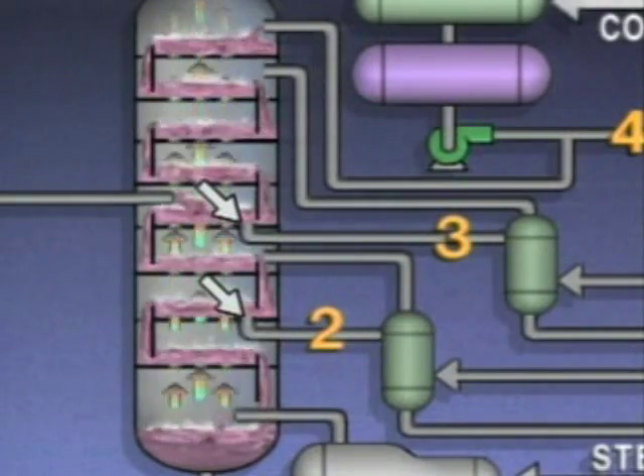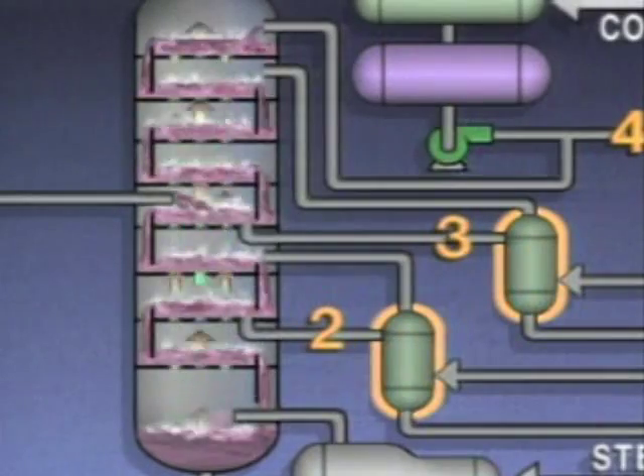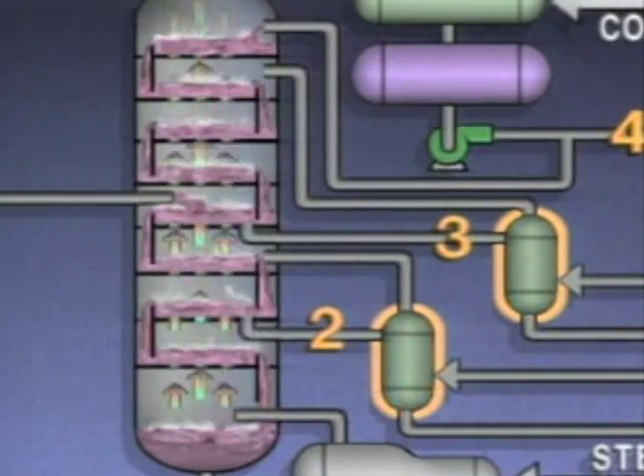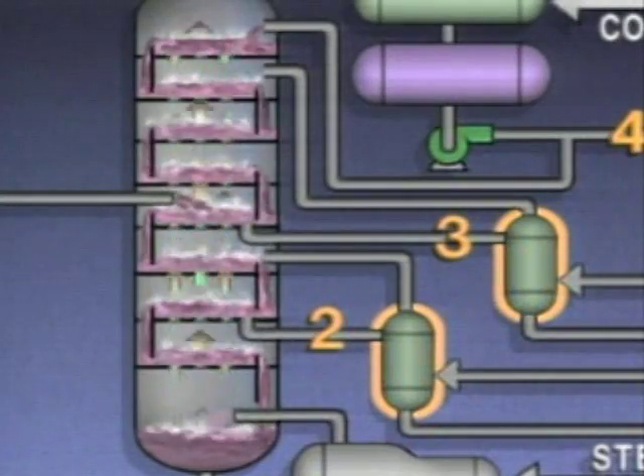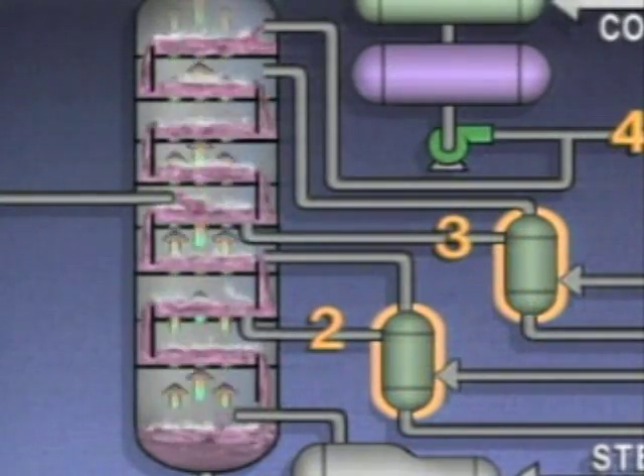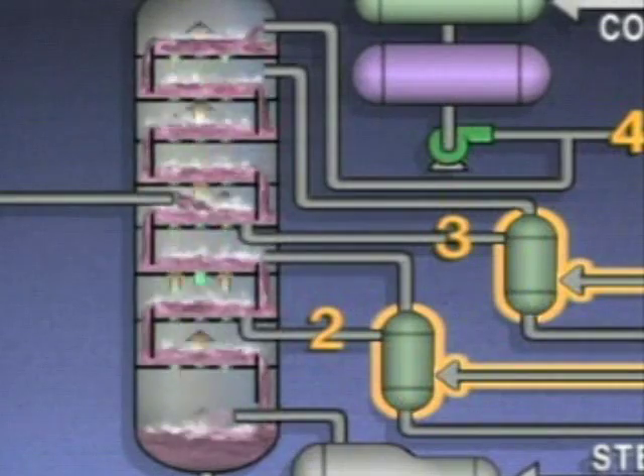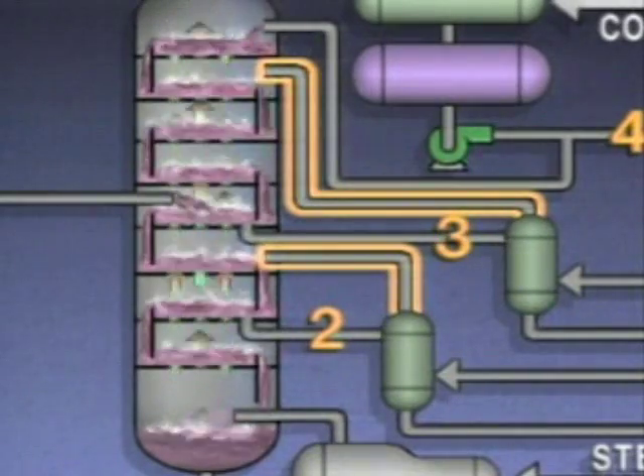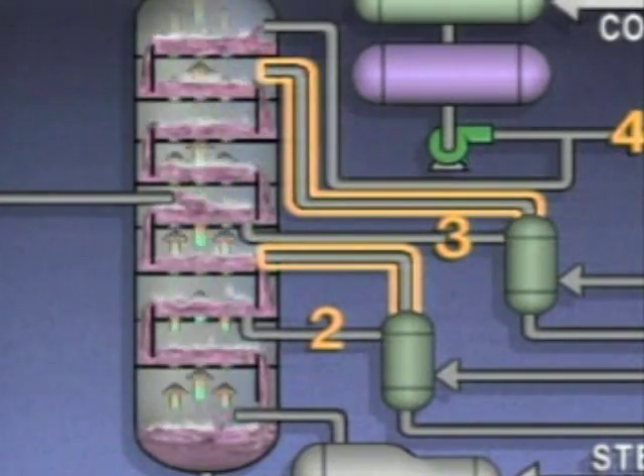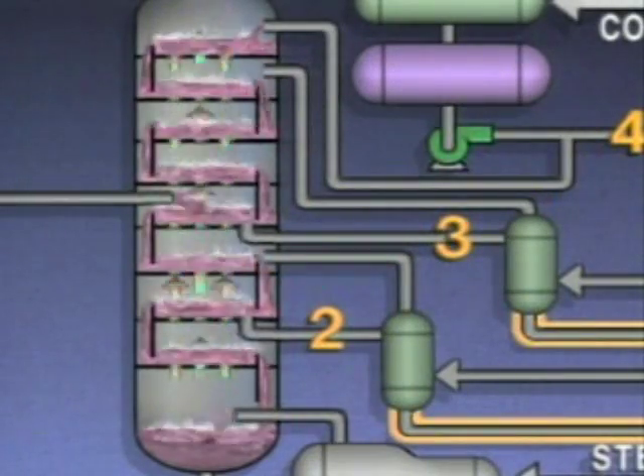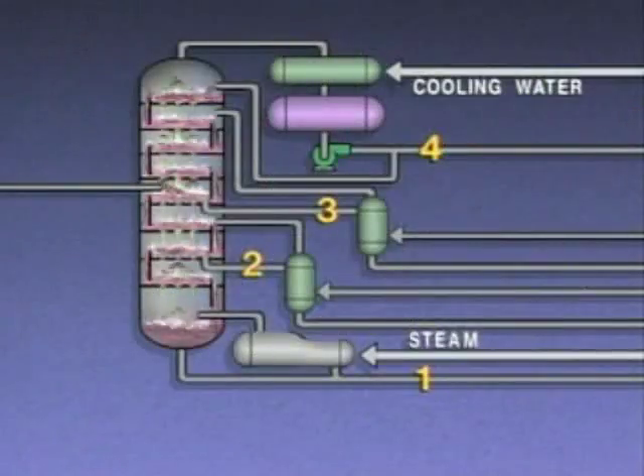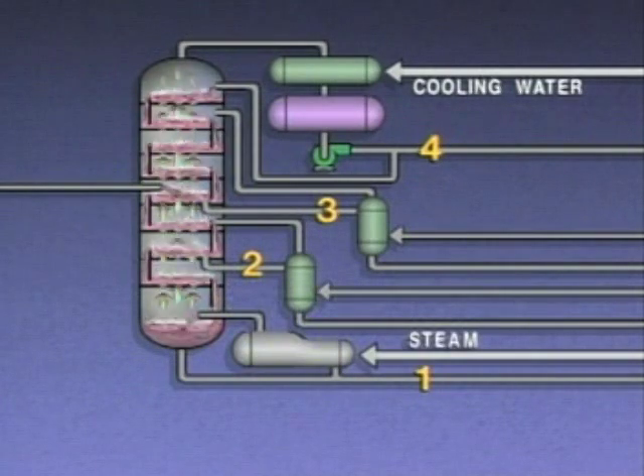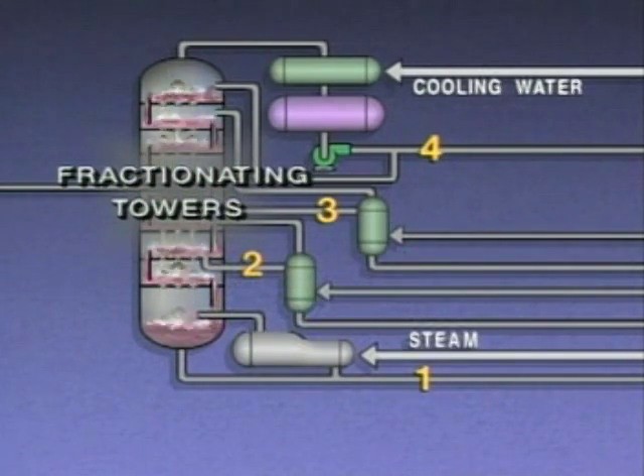The liquid drawn off by each side draw line goes to a side draw stripper. Each stripper is basically a small distillation tower. Its function is to remove or strip off any lighter products from the liquid. Liquid from the tower enters at the side of the stripper, where it is heated by steam, causing any lighter products to vaporize. The vapors produced are reintroduced into the tower above the tray from which the original liquid was drawn off. The liquid left over in the bottom of the stripper is drawn off as a product. The products or cuts obtained from distillation are sometimes called fractions, which is why distillation towers are sometimes called fractionating towers or fractionators.